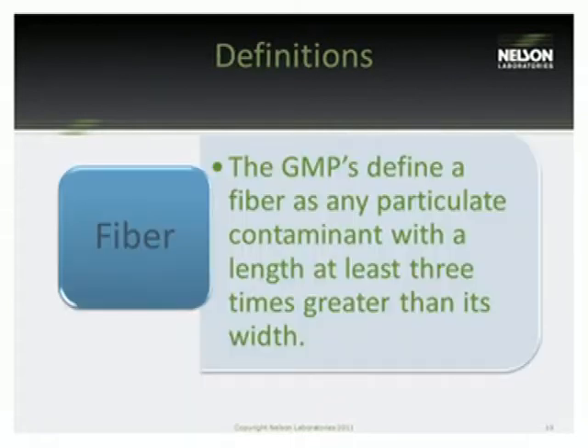Fibers often come up as a concern to some regulators as well as manufacturers, because of the nature of fibers, they can be very long but rather narrow. It's sometimes difficult to size fibers. It's not necessarily difficult to size them longitudinally, but sometimes a TAPPI chart or other reference may be used when sizing fibers due to their odd shape. Also, the light obscuration counter sometimes has a difficult time sizing fibers, especially if it's trying to size it longitudinally, and the maximum range of the machine may be too small to size a fiber accurately. The GMP's definition of a fiber is particulate matter with a length at least 3 times greater than its width.